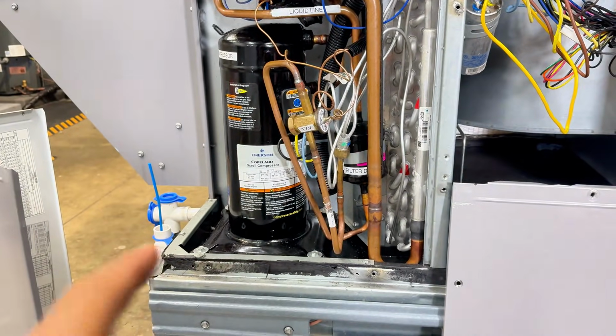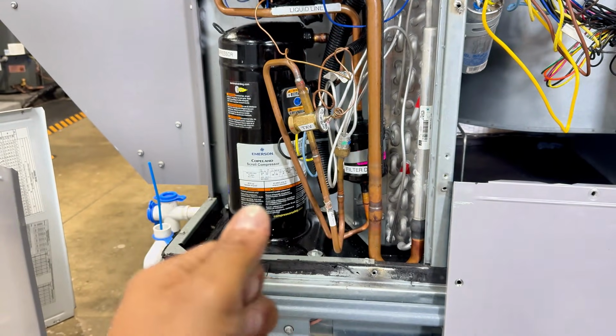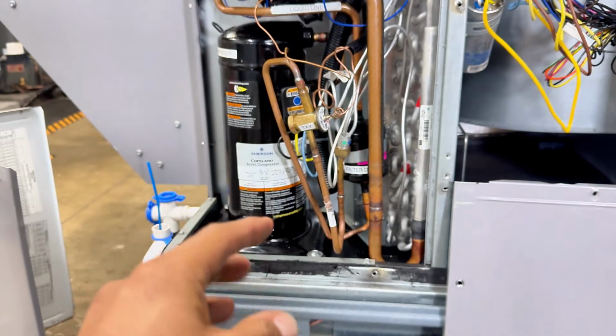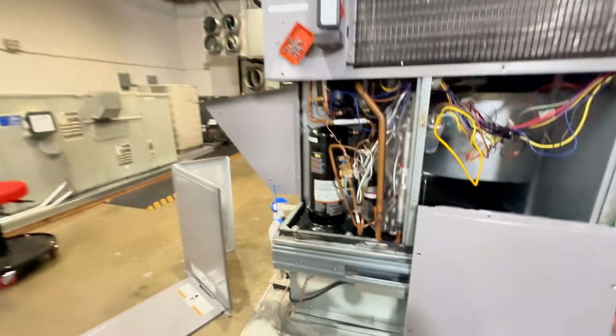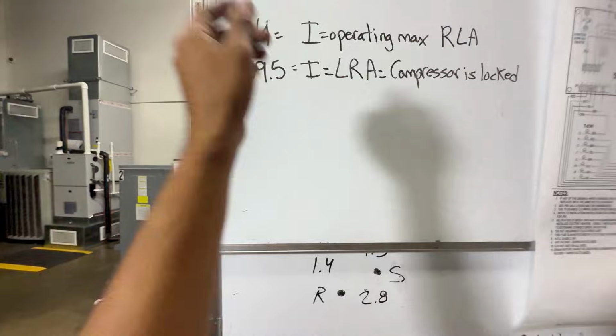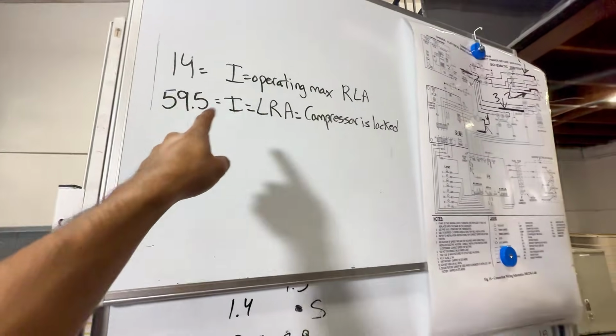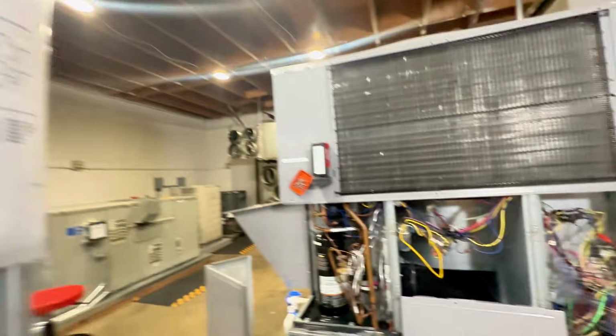And you're going to see how I fluctuate that number with some of the scenarios I'm going to be creating. So we already have the running load amps, rated load amps rather. In this case, they have it as operating max. And just one quick thing, I know that it's amperage because on the Ohm's law table, I refers to your current, your amp draw. So these are the numbers, just to have in mind.